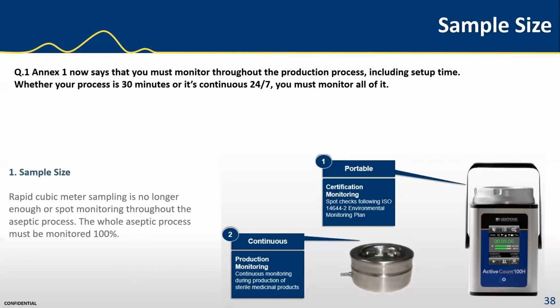That's really important here, that there is a requirement now to monitor your viables continuously during the process, and it talks about settle plates and active air samplers. Now we do have portable units and continuous monitoring devices. Here we see the sample heads. They connect to vacuum systems, and you basically lift off the lid, put in the agar, the Petri dish. The same here with the portable. Take off the lid and add the Petri dish, and away you go sampling. You're going to capture the location, you're going to capture sample volume, the sample times, and in some cases with the right software, you can capture the operator as well doing the sampling.